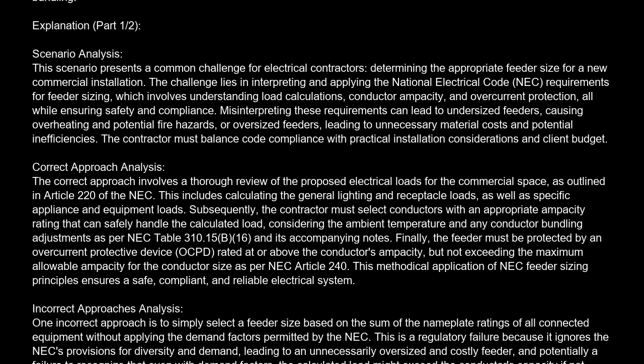Misinterpreting these requirements can lead to undersized feeders, causing overheating and potential fire hazards, or oversized feeders, leading to unnecessary material costs and potential inefficiencies. The contractor must balance code compliance with practical installation considerations and client budget. Correct approach analysis.